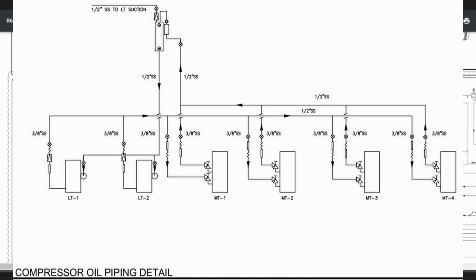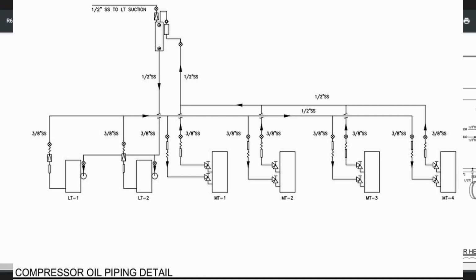Gotcha. And you said there was an additional line that was hooked up to the oil system somewhere. Is that correct? Yes, you're correct. The line, it doesn't show on this drawing, but the line coming from the evaporators, the oil drain line, ties into that line that is coming off the MT crankcases right at the reservoir. Oh, okay. So it just goes right into the reservoir.